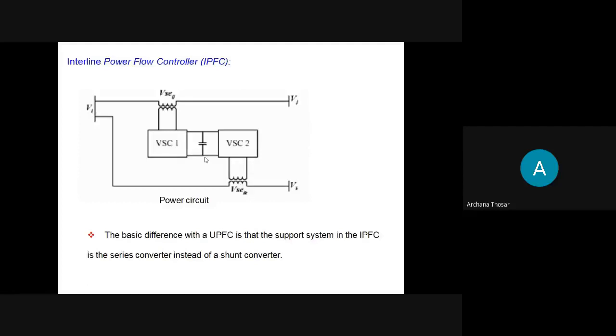Both the controllers are connected in series. There will be static synchronous series compensators connected, and they have a separate converter - every line will have a separate converter, and then the controller will be common. So basically IPFC also allows real and reactive power to flow between the lines.